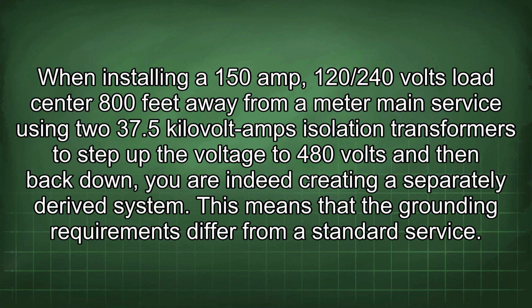When installing a 150 amp, 120/240 volts load center 800 feet away from a meter main service using two 37.5 kilovolt amps isolation transformers to step up the voltage to 480 volts and then back down, you are indeed creating a separately derived system. This means that the grounding requirements differ from a standard service.